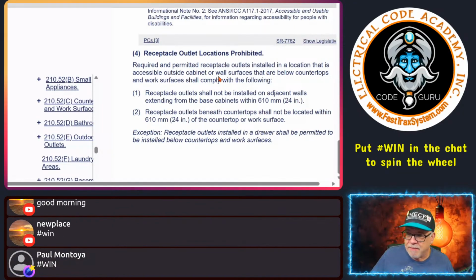So at the end of the day, required and permitted receptacle outlets installed in a location that is accessible outside of the cabinet or wall surfaces that are below the countertop and work surfaces shall comply with the following. So where you may have a receptacle that is down low to meet the wall space requirement, that's okay. The code is saying now this is okay. And again, it didn't really say that in the 2023. It just kind of was a prohibiting statement.